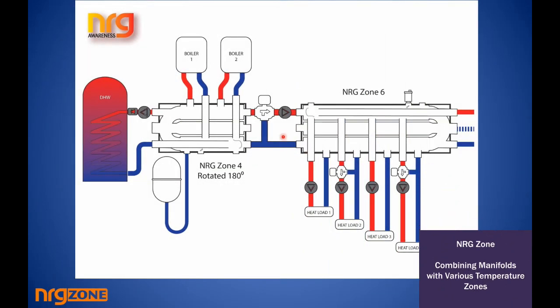Now here we look at, so what I was saying, you mentioned roughly earlier, where you might be collecting heat into a manifold, say from 2 boilers. You have your pressure vessel connected onto your neutral point. You might have your filling point in here. And now your high temperature water is taken directly to a high temperature unit, such as a calorifier or heat cylinder, domestic water cylinder, whatever.